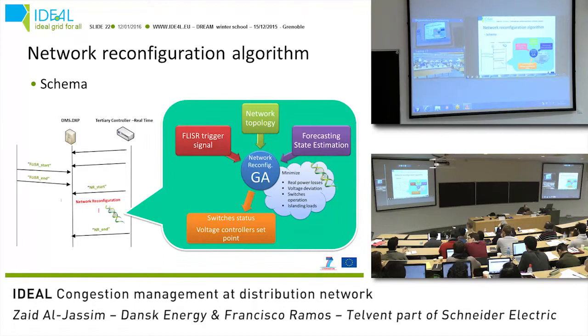As Paco explained, the field crew team will try to locate the fault event and restore the fault, and then communicate with the network reconfiguration algorithm, which is a part of the tertiary controller at the control center level, to restore more customers, or as many customers as possible. So here you can see a little overview of the network configuration algorithm and how it's triggered.